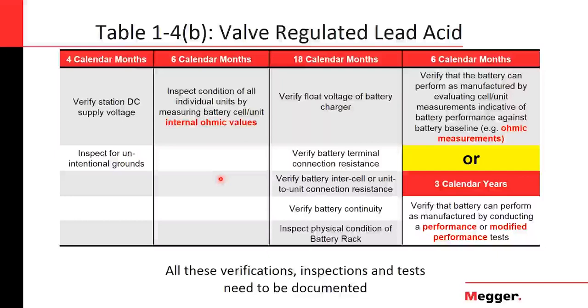And every 18 calendar months, you have basically the same verifications or the same measurements as for the lead acid batteries. If you take a close look at those, mainly it is to verify that there's a good operating circuit through the battery. Three of those tests will confirm the same thing, that you have continuity, a good path for current to flow through the battery. And then there's the requirement to verify that the battery can perform as the manufacturer specified. Again, you have 2 options. You have the ohmic measurement every 6 calendar months, or a discharge test every 3 calendar years.